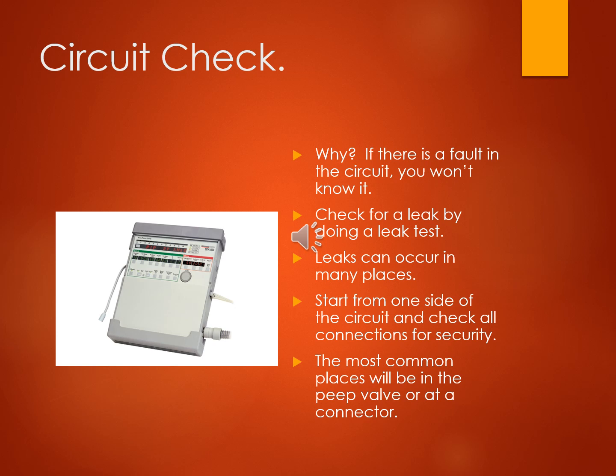You check to see if all the lights light up and the noises that the ventilators are supposed to make are doing what they're supposed to. If you do have a leak, make sure you start from one side of the circuit and check for that leak that way. A lot of times on these ventilators, the connections are the points that they have a leak. So we backspin those, the flow sensor and the pressure sensor.